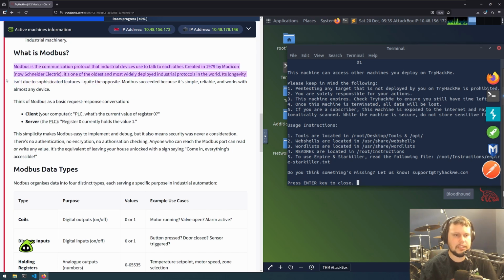Its longevity isn't due to sophisticated features, quite the opposite. Modbus succeeded because it's simple, reliable, and works with almost any device. Think of Modbus as a basic request-response conversation. So you've got the client, PLC, what's the current value of register 0? Then the server, PLC, register 0 currently holds value 1.